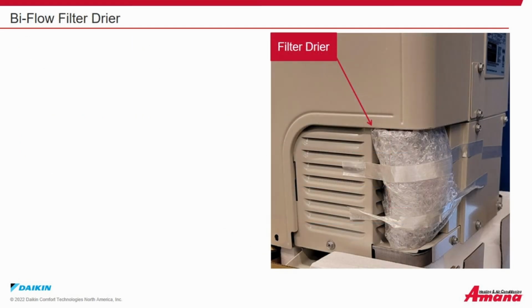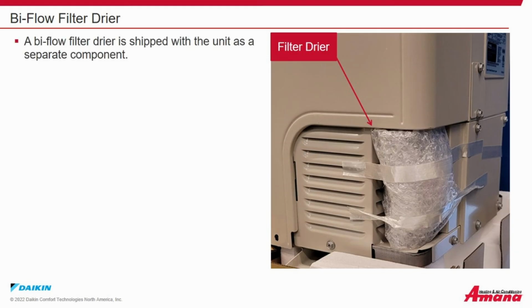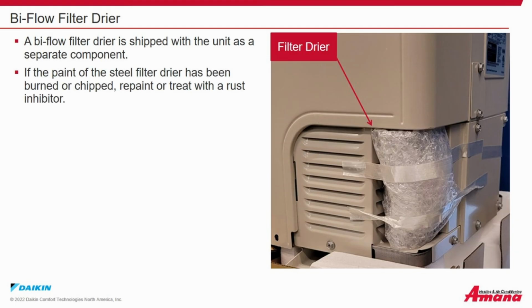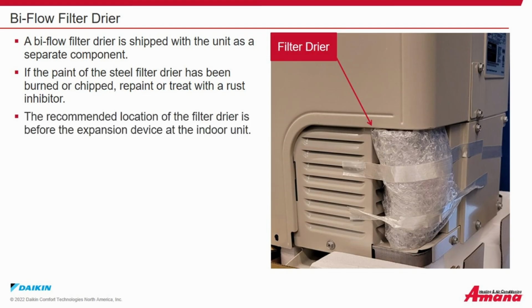Biflow filter dryer. A biflow filter dryer is shipped with the outdoor unit as a separate component. If the paint of the steel filter dryer has been burned or chipped, repaint or treat with a rust inhibitor. The recommended location of the filter dryer is before the expansion device at the indoor unit.